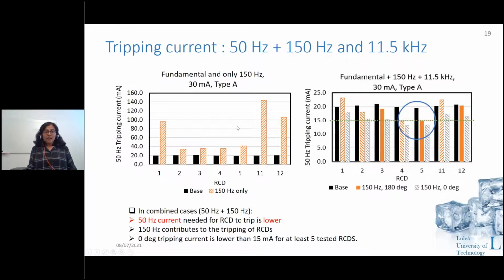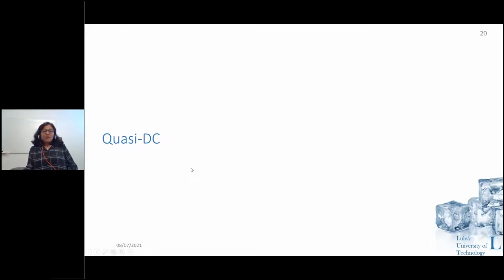But above this frequency, like for 250 hertz, 350 hertz, some RCDs tripped, but some RCDs did not. We have tested up to 1000 hertz, and some of the RCDs tripped and some did not trip. But for 150 hertz, all of the RCDs tripped. So for type A RCDs, from this we concluded that if you have a 150 hertz component, then it contributes to the tripping of the RCD. It increases the chances for the RCDs to trip. And yeah, next is quasi-DC.